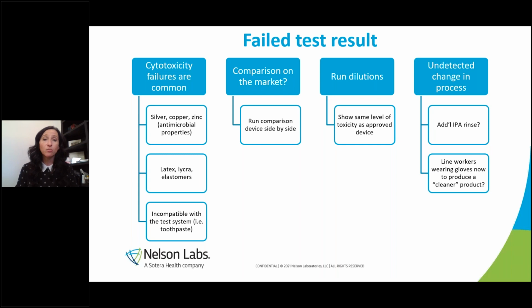Maybe there's an undetected change in your process. We had a company add an additional IPA rinse because they wanted their device cleaner. And even though we think IPA evaporates, enough of it sticks around that they started to fail their routine cytotoxicity monitoring tests. And we had another case where somebody said, hey, everybody wear gloves because you're touching the product. We want it to be clean. And they started to fail their cyto because the latex powder was coming off the gloves onto the product. So, you know, just some things to think about how to troubleshoot and think about that. Maybe you say, oh, nothing's changed in our process. Any change is a change, right? Even if you think, oh, it's making it better, it could be impacting things down the road. With the IPA rinse, we just said rinse with water after that.